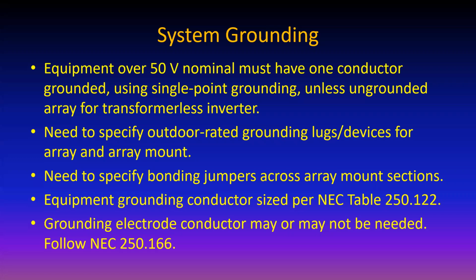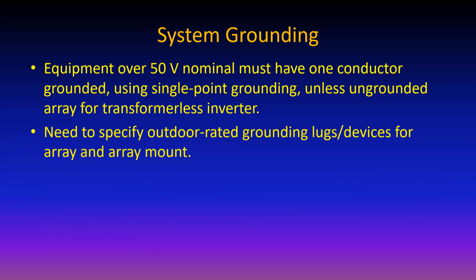On the other hand, if you put the array on the roof of a garage and then feed it to a panel in the house, you'll probably need to drive a ground rod or two at the location of the garage and have a grounding electrode conductor there. So again, pay careful attention to 250.166.